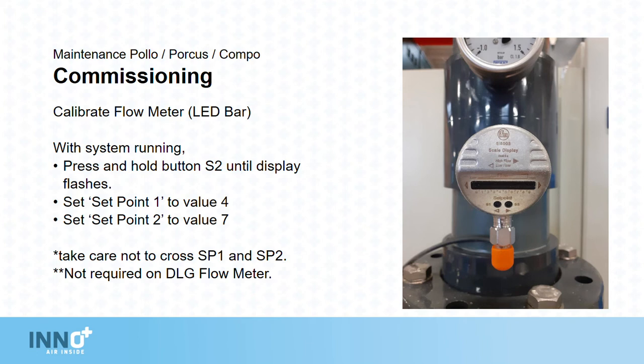Calibrate the flow meter, or the LED bar. With the system running at 100%, the correct pressure and full flow, press and hold button S2 until the display flashes. This calibrates the flow to show 100%.